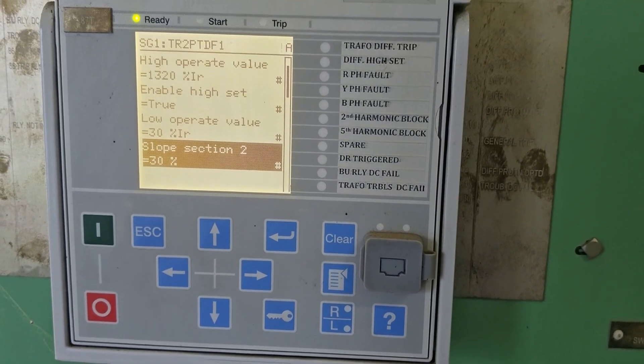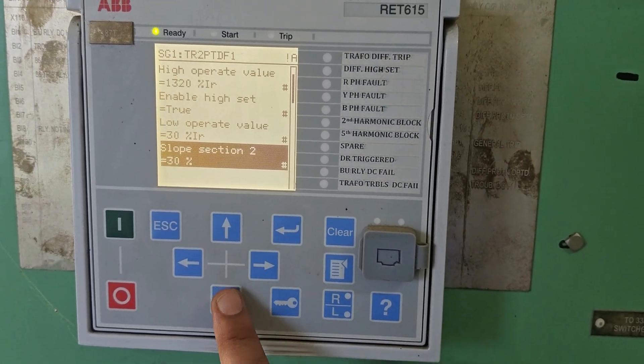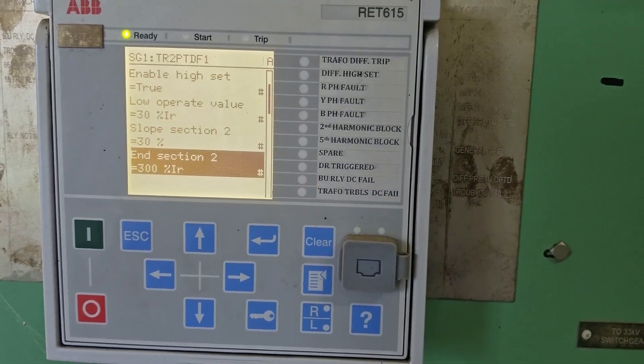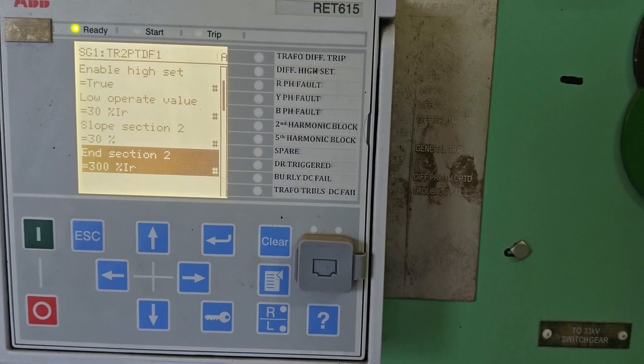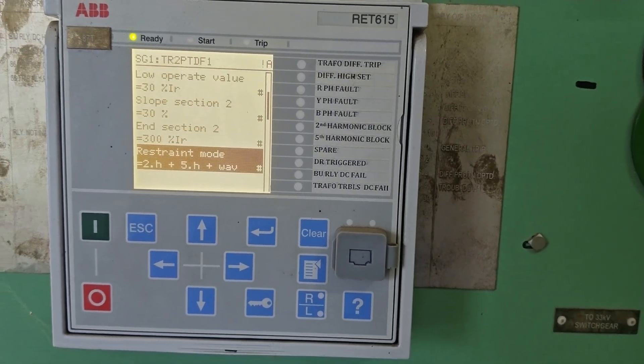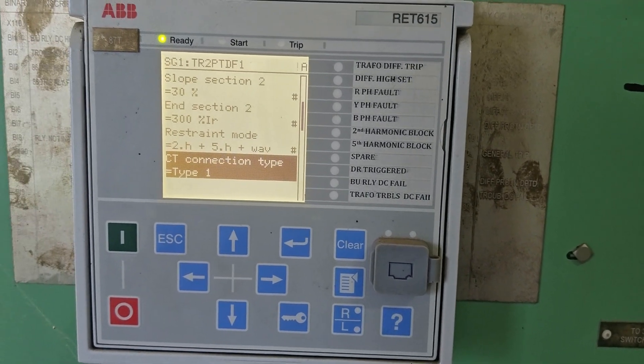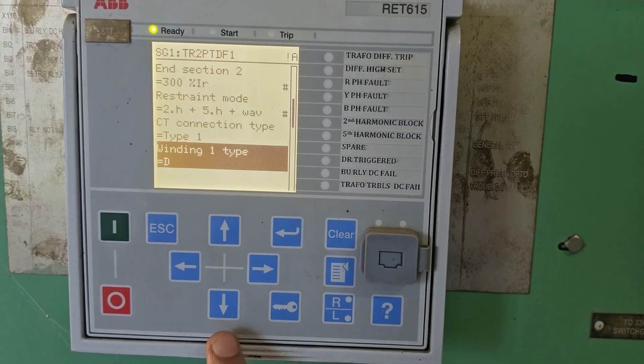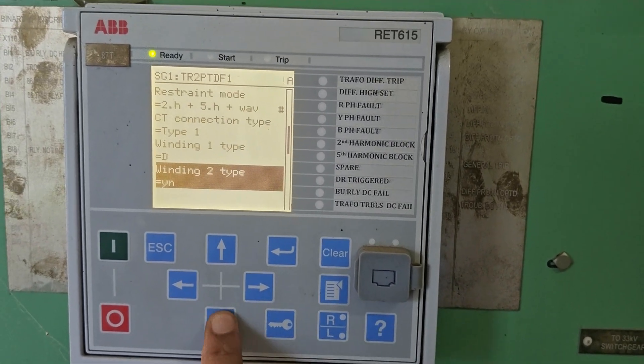To conclude the slope section: a 30% setting ensures that the relay has balanced sensitivity — tripping for internal faults while maintaining stability during external faults or CT saturation conditions.